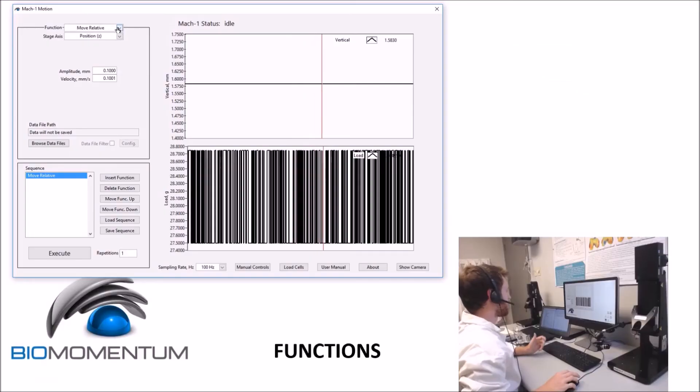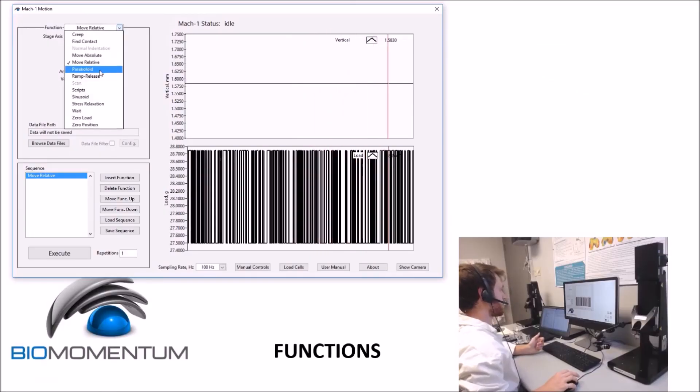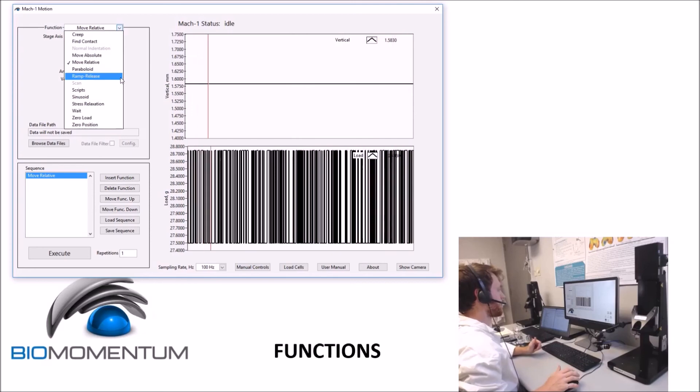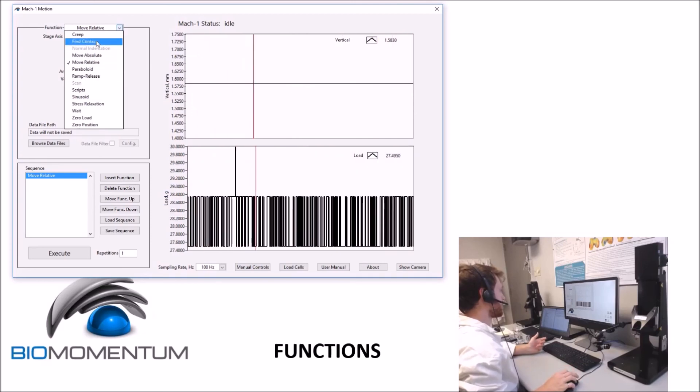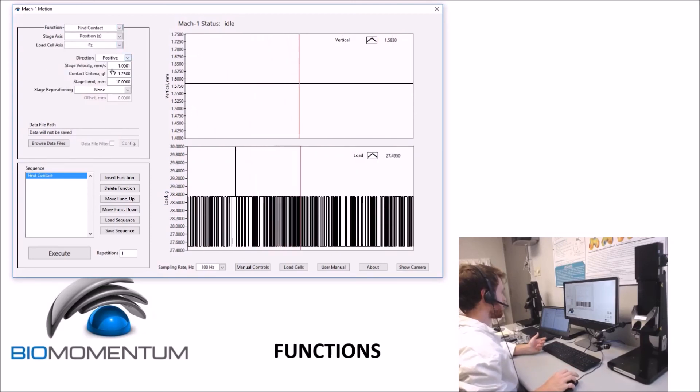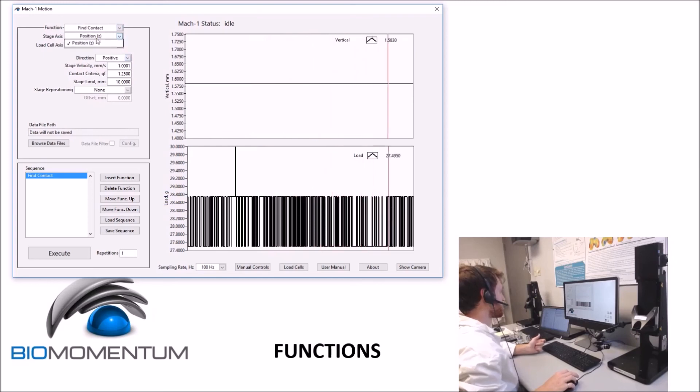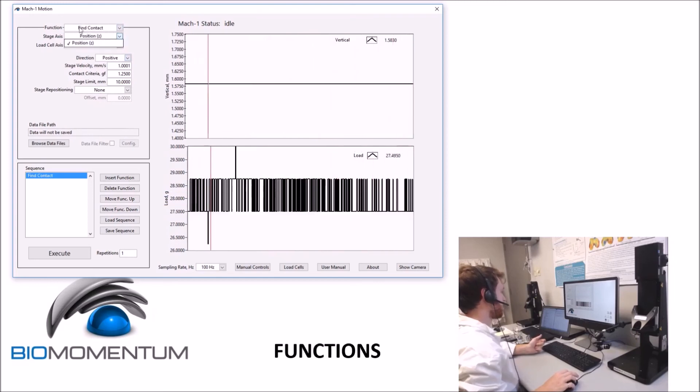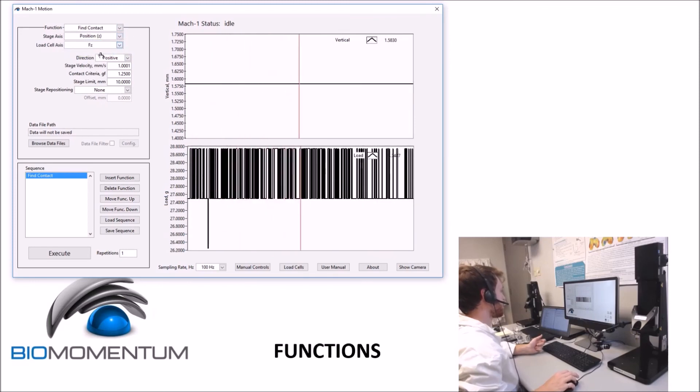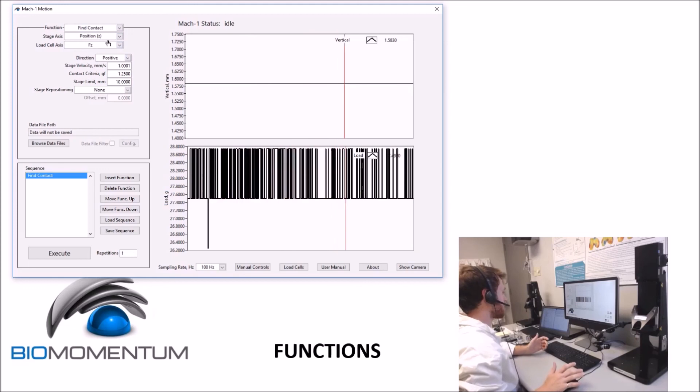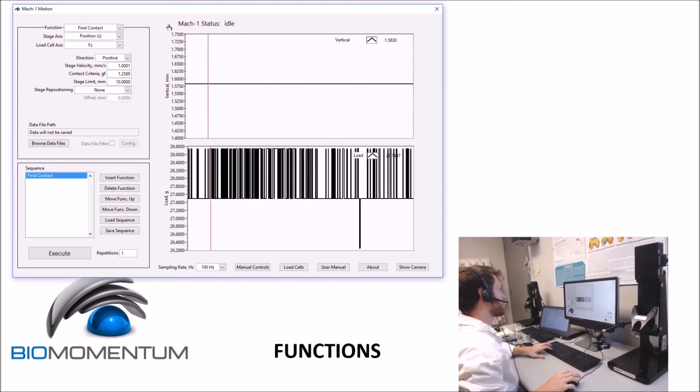The function menu is a drop-down list of all the available functions that can be used to build a sequence to perform a test. As each function is selected, the corresponding configurable parameters with the recording units are displayed. For each function, the user must specify both the stage axis as well as the load cell axis, and failure to match these two can result in damage to the load cell, because the stop criteria might never be met, for example.